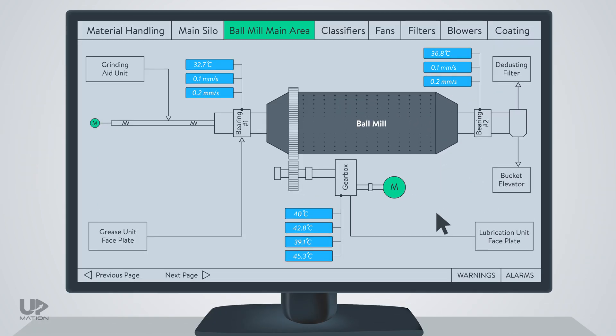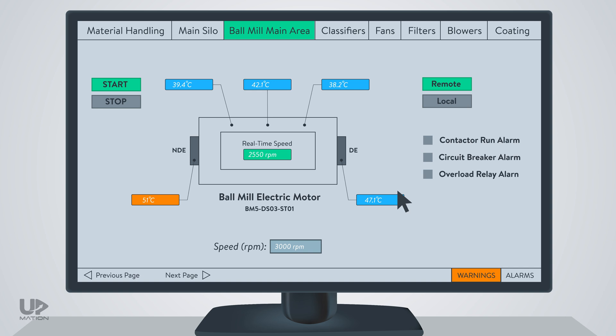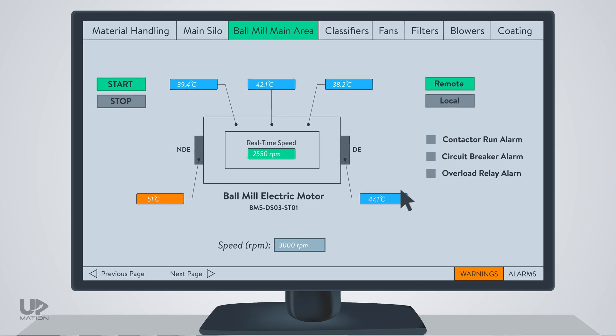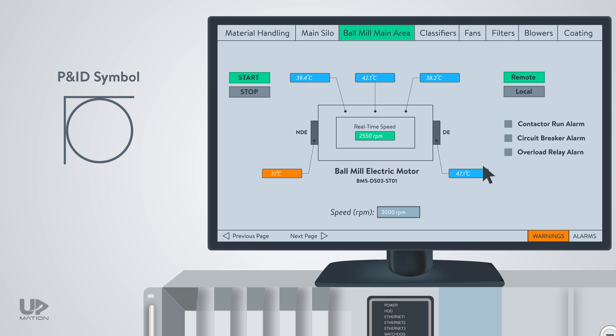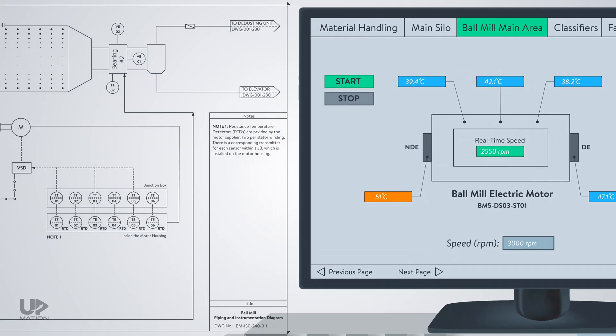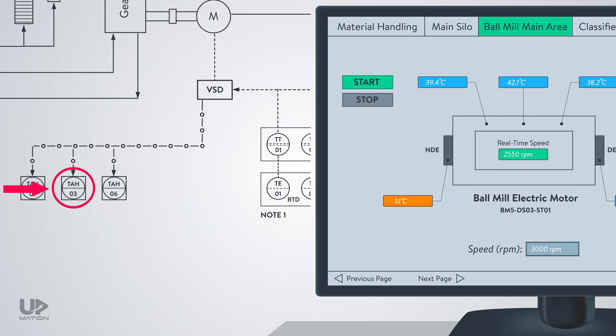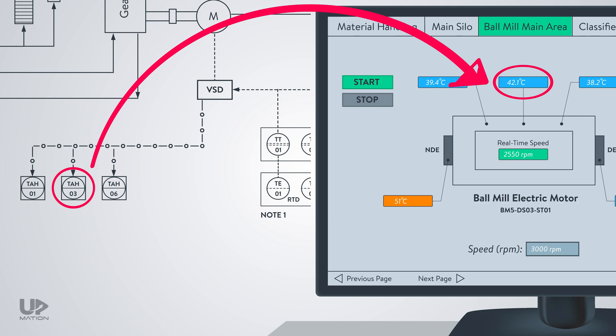In this way, through the human-machine interface or HMI, if the operator opens the related pages for the ball mill motor, he or she should observe the motor winding temperature indicators. Inside the P&ID, I use a circle-in-square symbol to indicate that the operator will see those temperatures on their computer in real-time. In other words, each of these symbols in our P&ID equals one of these temperature readings in the HMI.